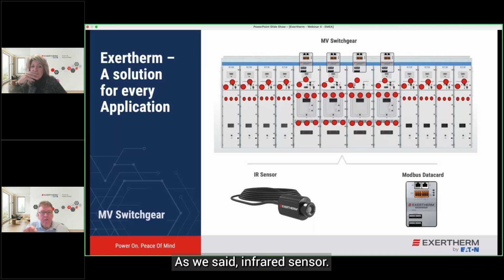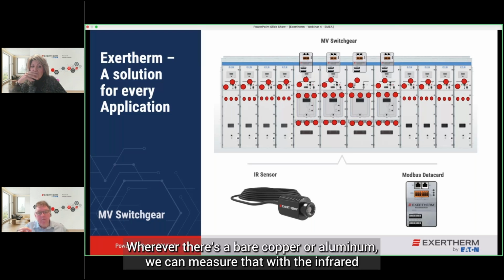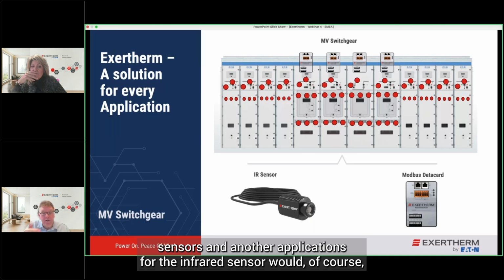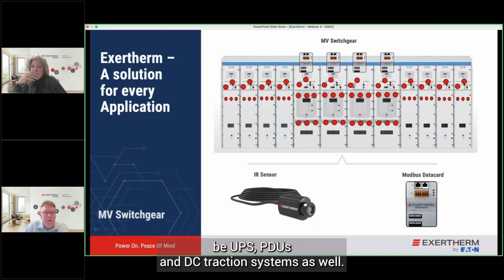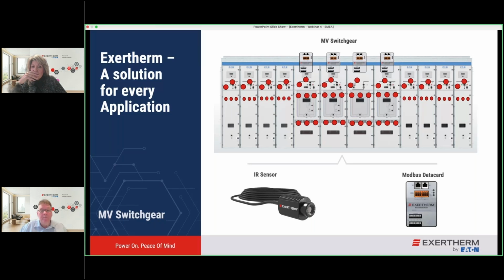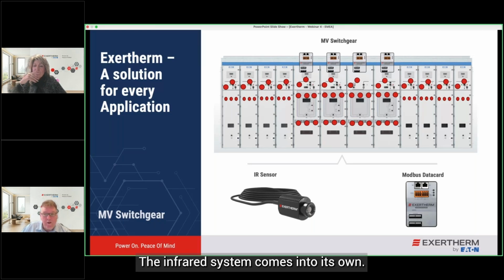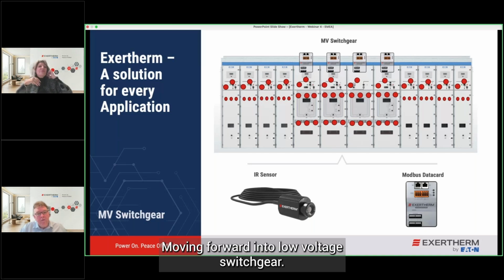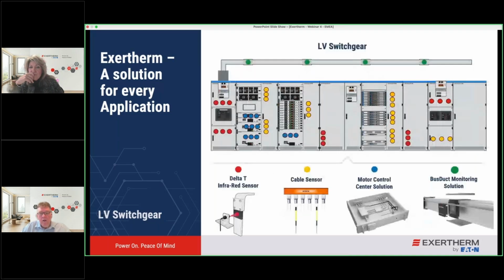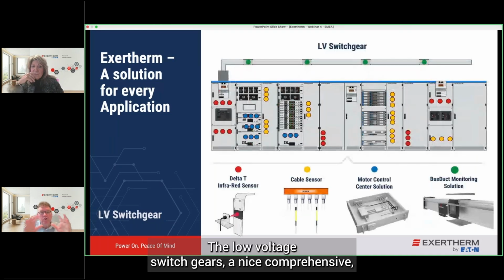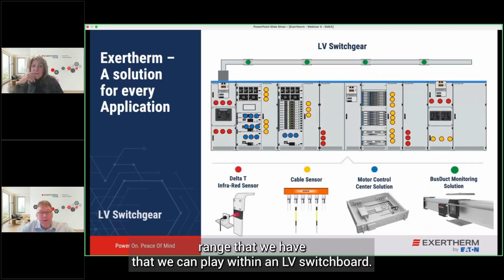As we said, with the infrared sensor, wherever there's bare copper or aluminium, we can measure that. Other applications for the infrared sensor would, of course, be UPS, PDUs, and DC traction systems as well. The infrared system comes into its own.